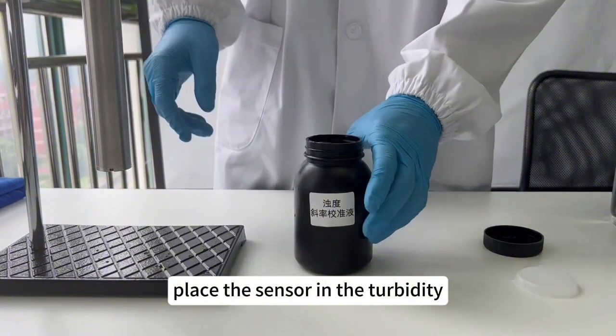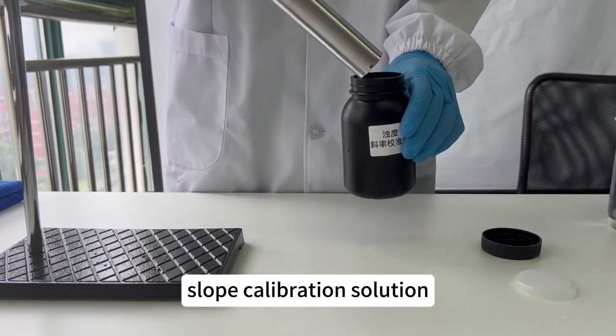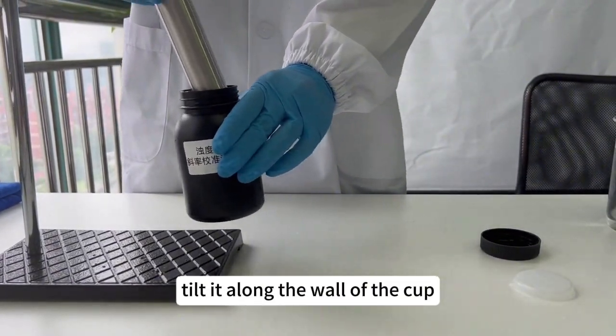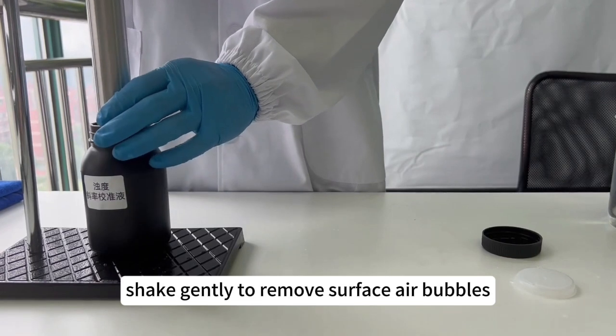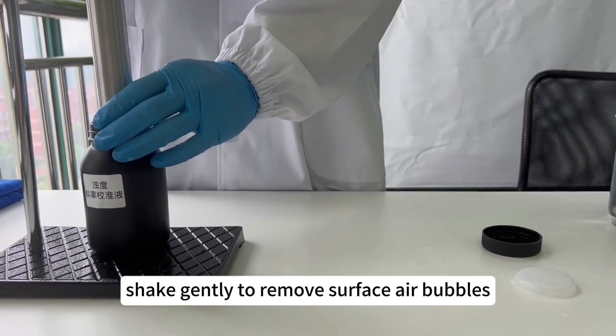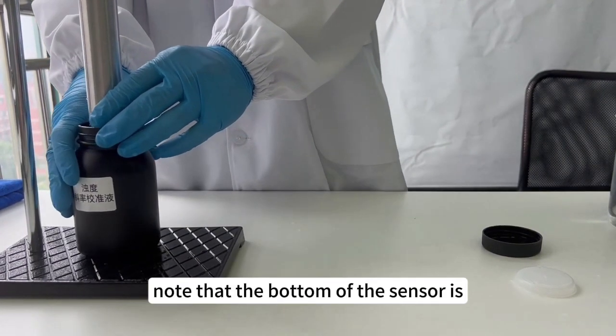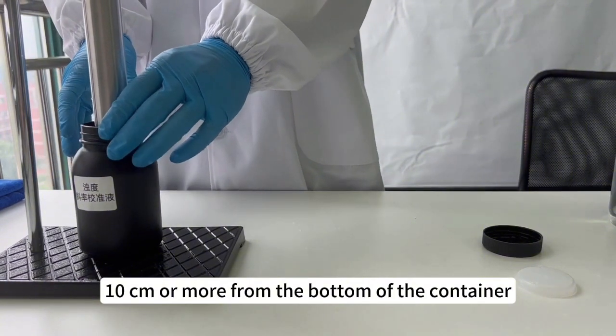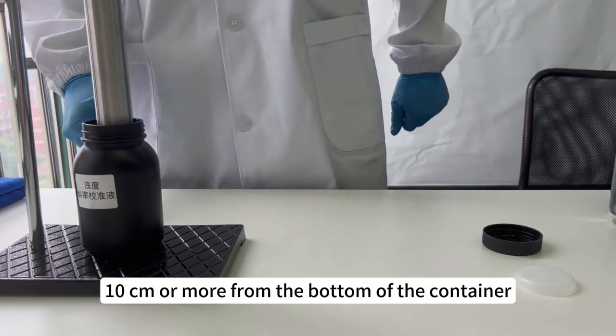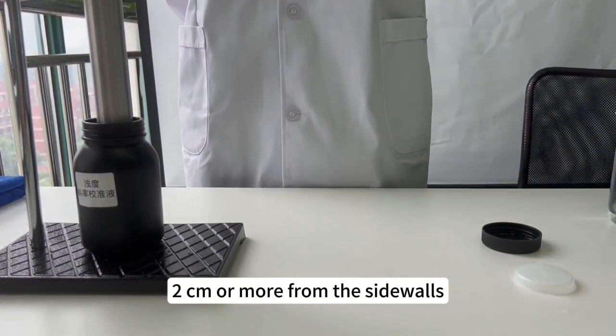Place the sensor in the turbidity slope calibration solution. Tilt it along the wall of the cup. Shake gently to remove surface air bubbles. Note that the bottom of the sensor is 10 centimeters or more from the bottom of the container, 2 centimeters or more from the sidewalls.